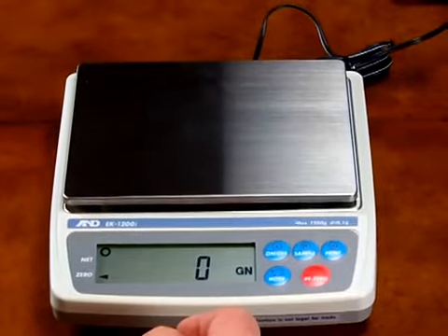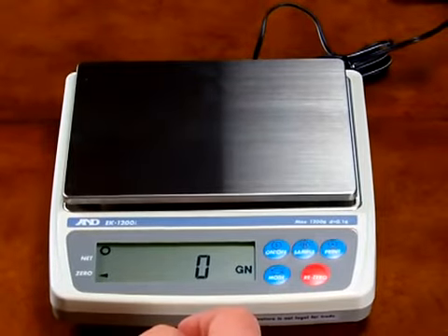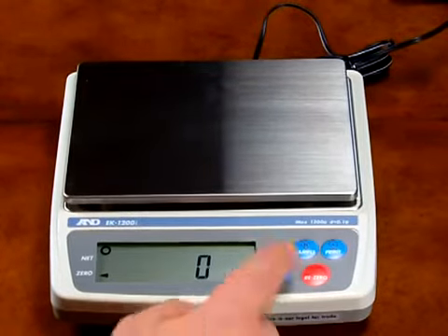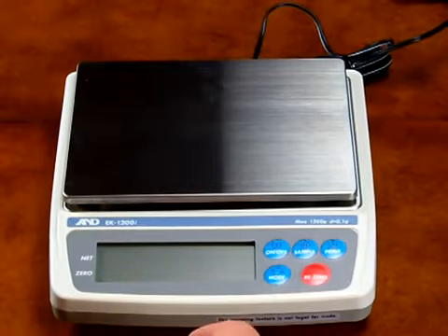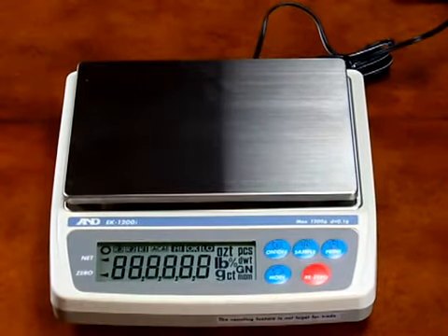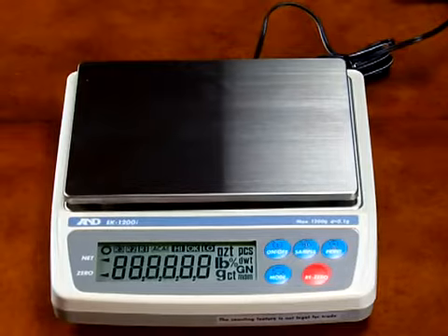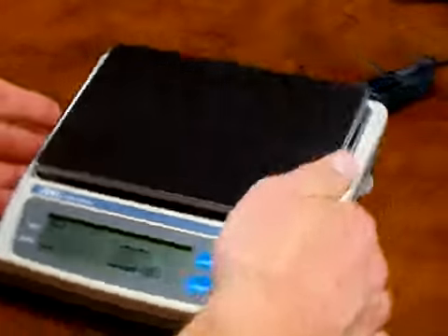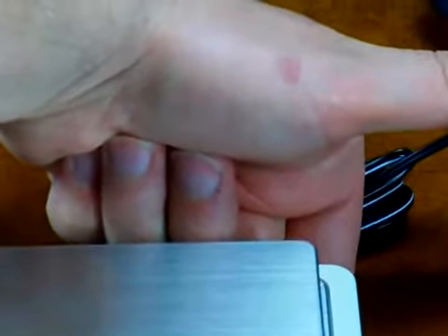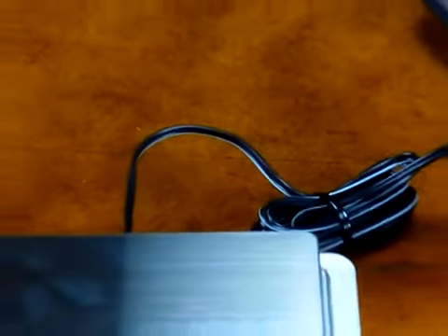The EK is much, much simpler than other legal for trade balances on the market today for calibration. So we'll shut the scale off, turn the scale back on, and we're going to go to the rear of the scale, the button that's on the back of the scale. I don't know if you can zoom in and see that little button. We're going to be pressing this button, and this is going to initiate the calibration. So we'll hold the button down in the rear of the scale, and we see Cal 0.